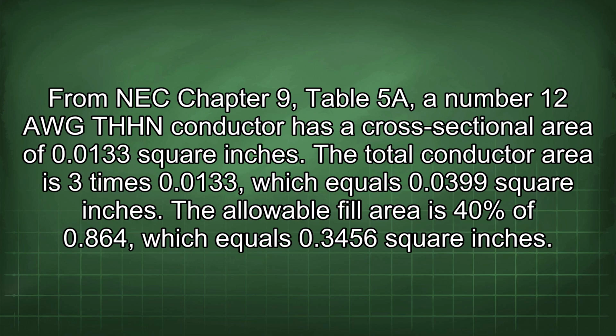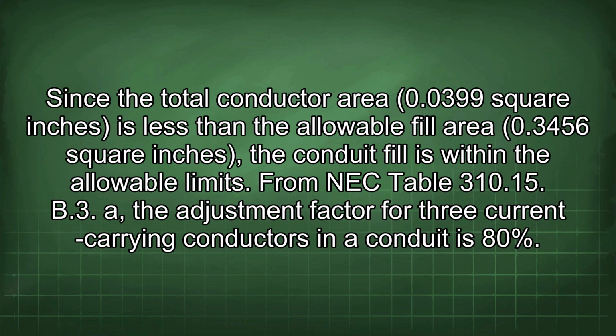The total conductor area is 3 times 0.0133, which equals 0.0399 square inches. The allowable fill area is 40% of 0.864, which equals 0.3456 square inches. Since the total conductor area 0.0399 square inches is less than the allowable fill area 0.3456 square inches, the conduit fill is within the allowable limit.